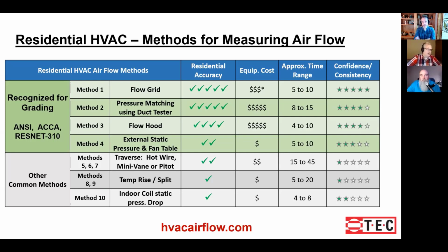The first column there after the description is the accuracy, and we just use sort of a checkmark scale to show which ones are more accurate, which ones are less accurate. 1 check is not very accurate, all the way up to 5 checks for the most accurate methods. And then the equipment cost, of course, that's purchasing the equipment, and that's an important consideration. But a lot of times people focus too much on the equipment cost and forget the next column over, which is their time. Some of these methods take as few as 5 minutes, but others take as much as 45 minutes, depending on how big the duct is and stuff like that.